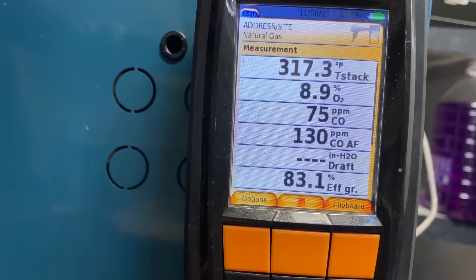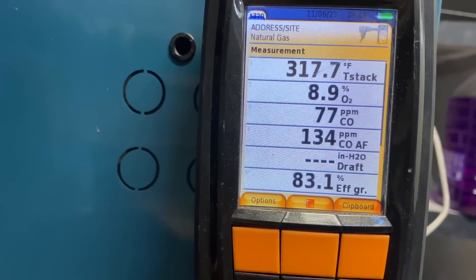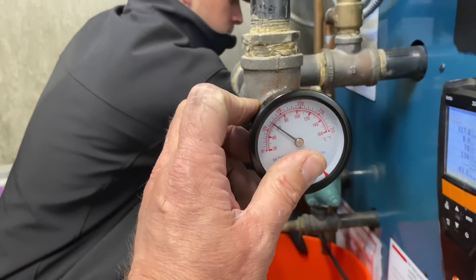Gross efficiency is 83.1%, CO2 of 6.73%. We haven't checked gas pressure yet, but that 74–75 parts per million CO is higher than I'd like it to be. We have a stack temperature of about 150 degrees.